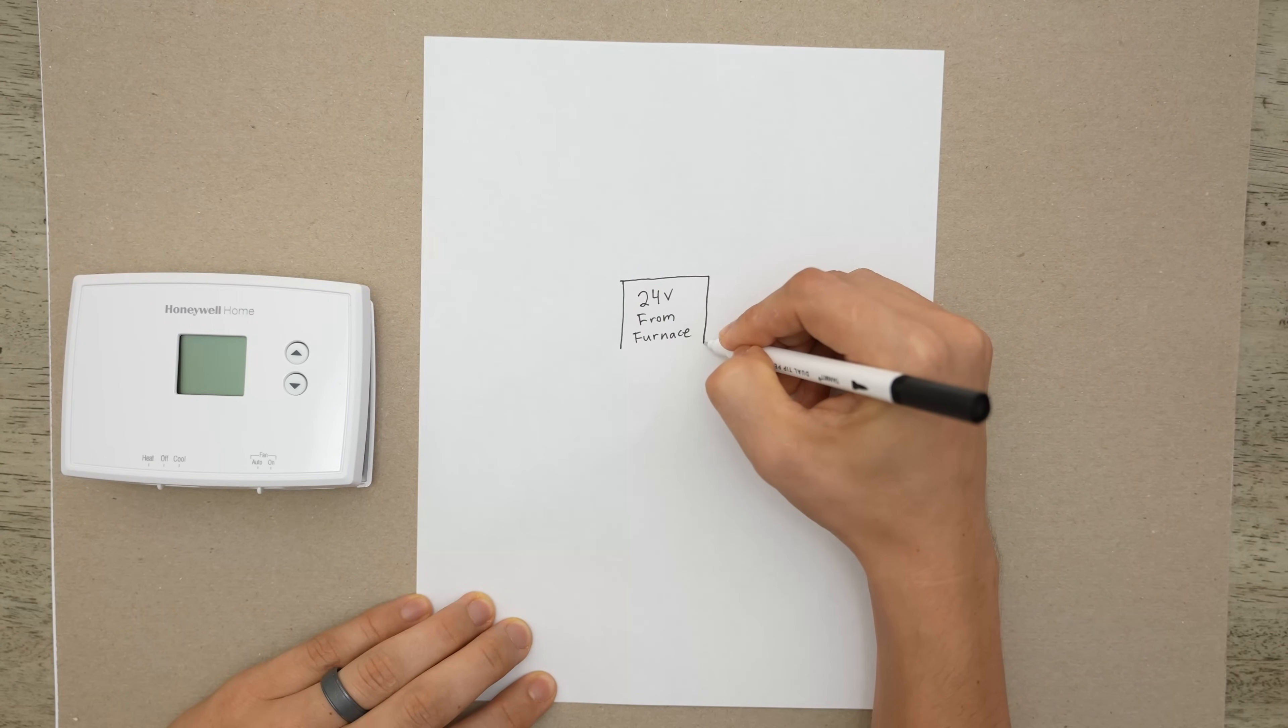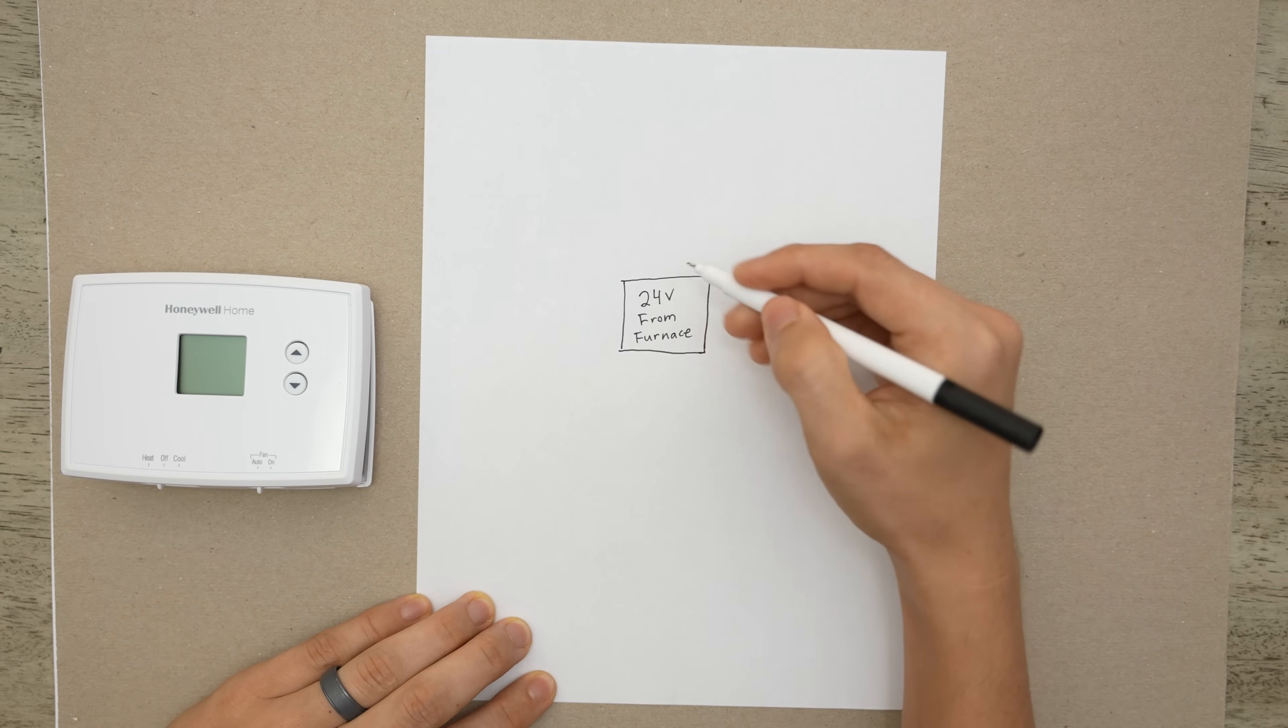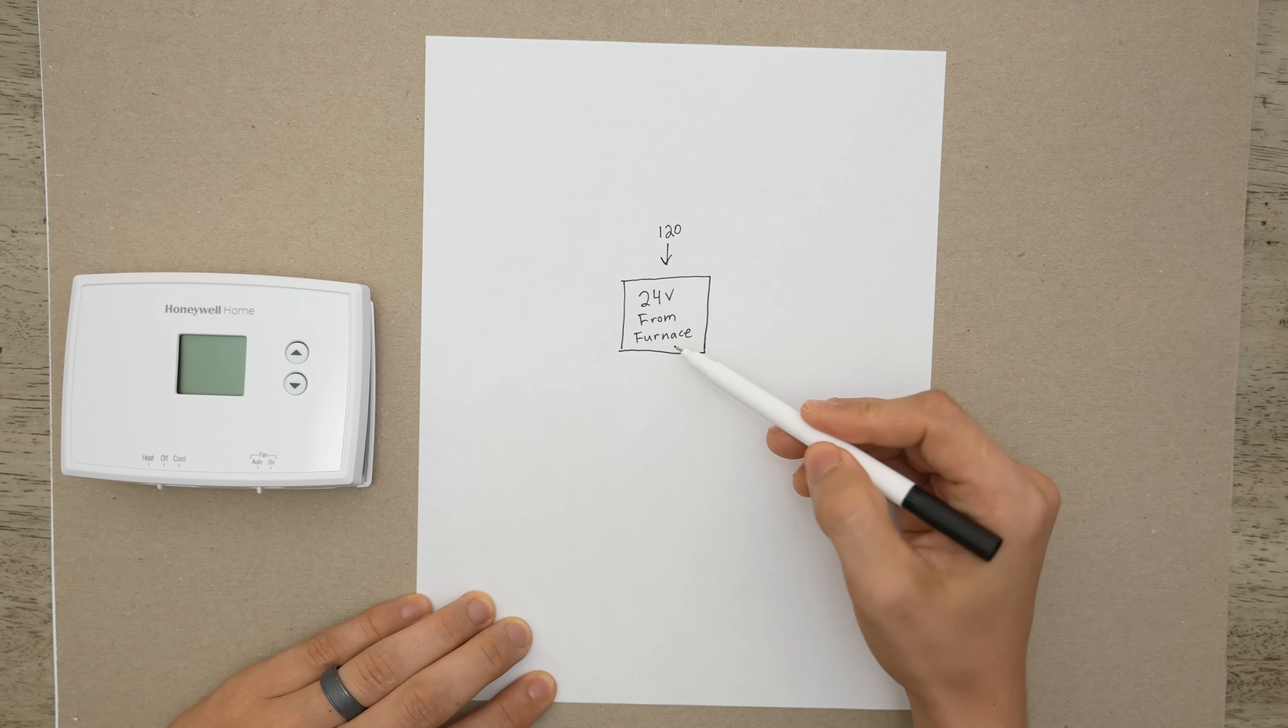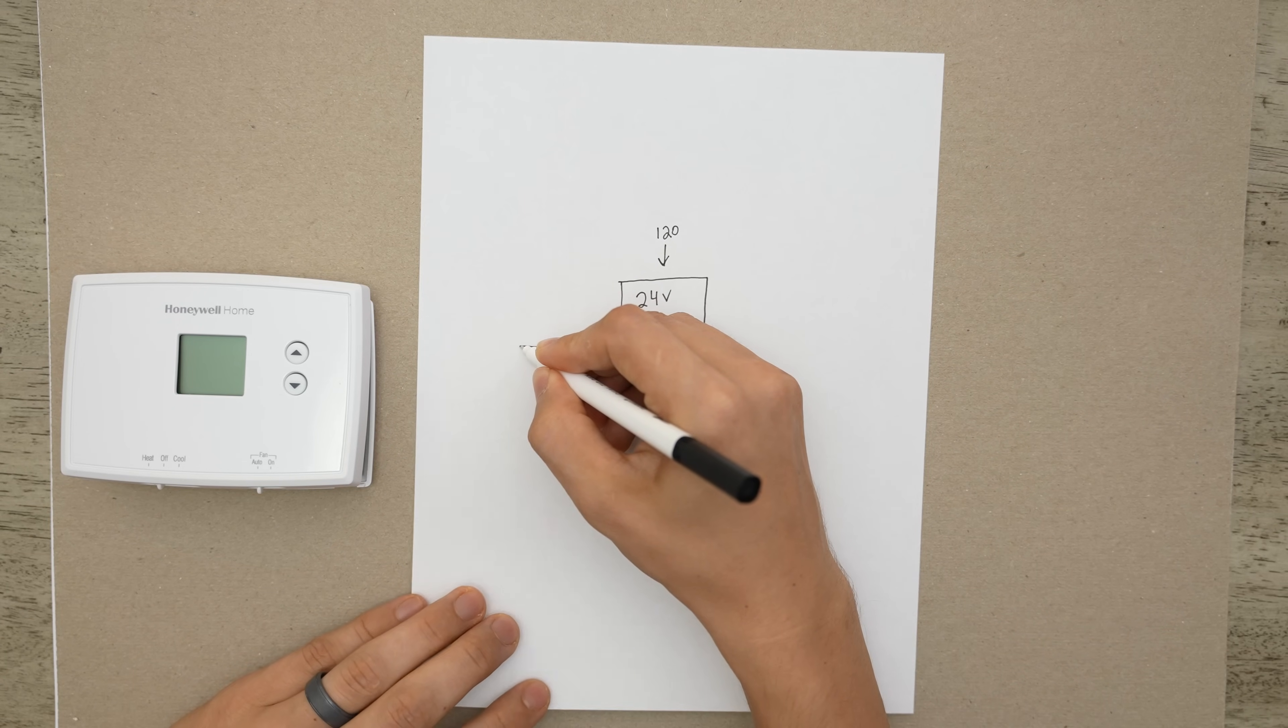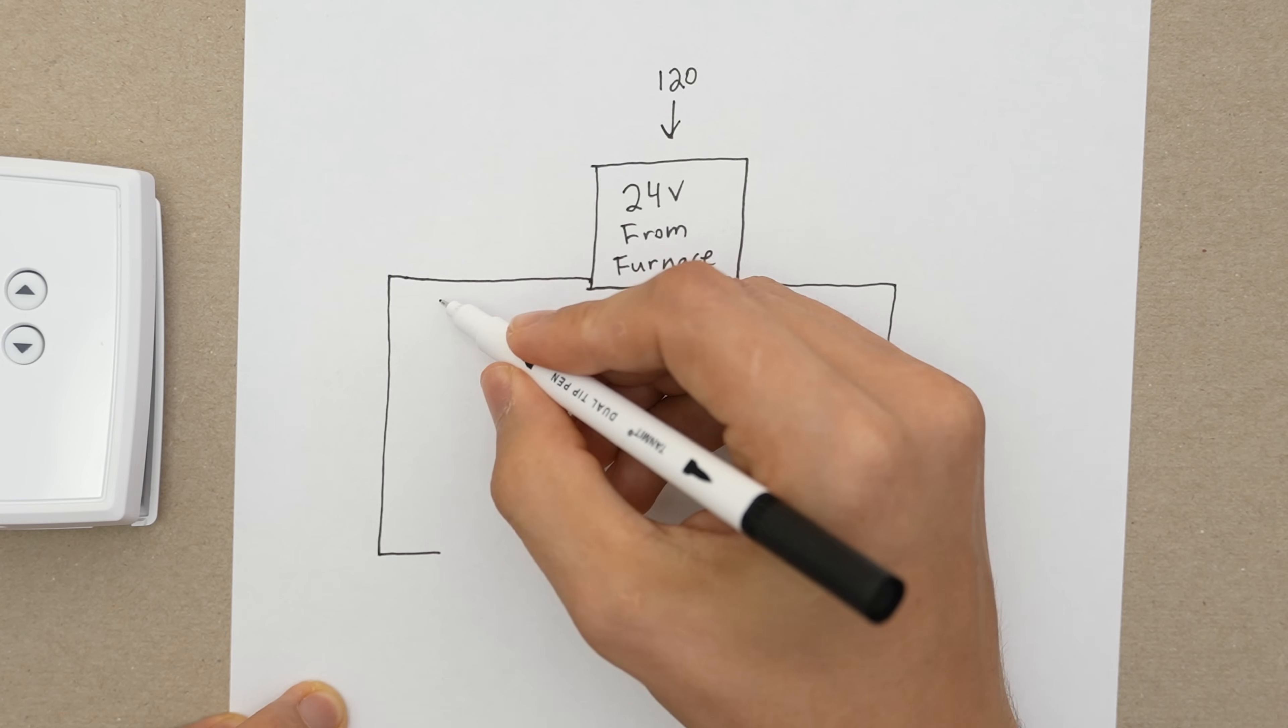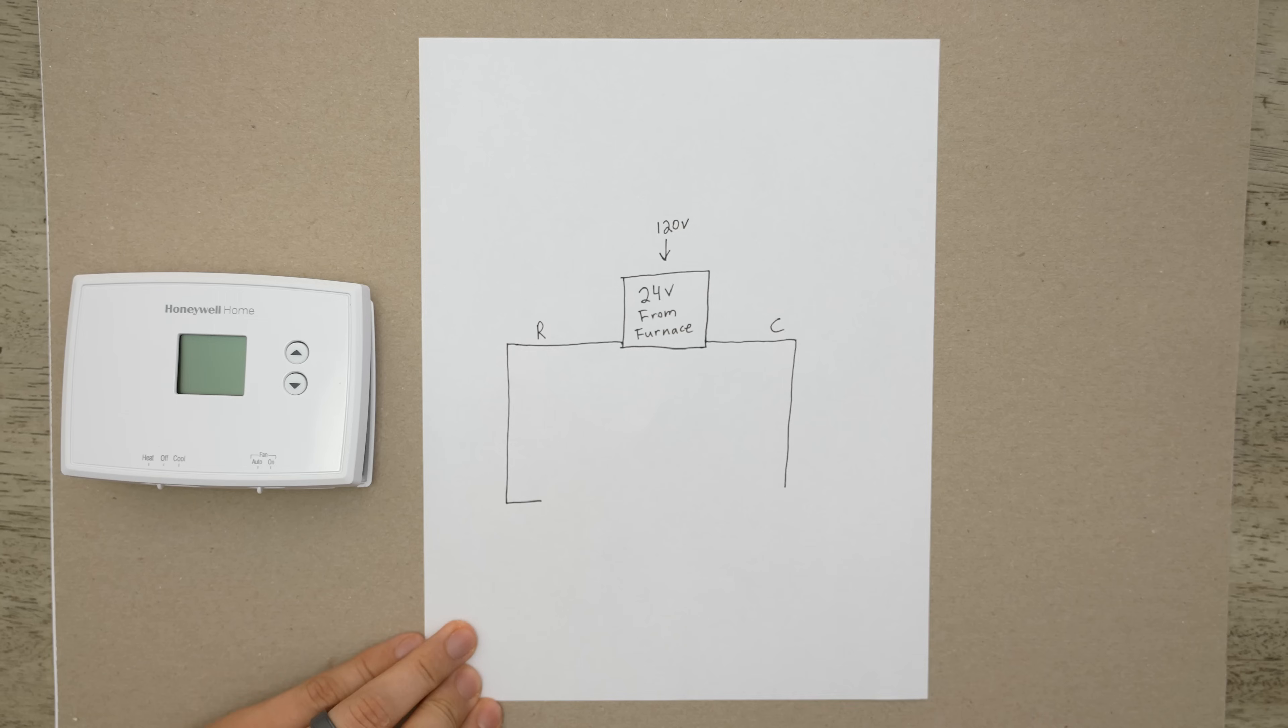The thermostat is getting its source, its power source, from the furnace. There's a transformer in there so we have 120 volts going in. The transformer turns it into 24 volts and then the control board sends that 24 volts to the thermostat in a typical application. So here is going to be our power line and this would be the common. So 24 volt hot, 24 volt common. This will be R for the hot leg and C for the common.